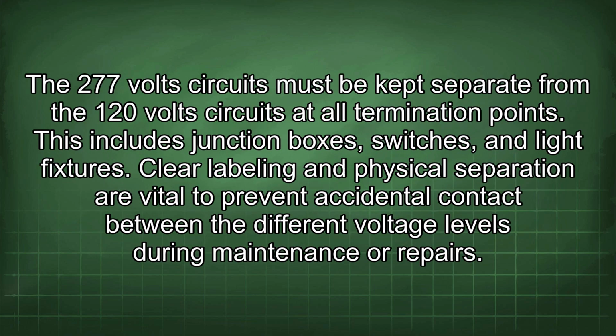The 277 volt circuits must be kept separate from the 120 volt circuits at all termination points. This includes junction boxes, switches, and light fixtures. Clear labeling and physical separation are vital to prevent accidental contact between the different voltage levels during maintenance or repairs.